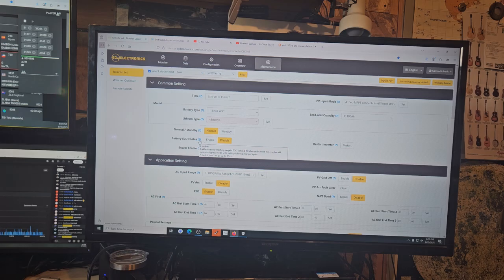Okay, so if enabled, when battery reaching on-grid EOD value and AC charge disabled, the inverter will switch to bypass mode until battery is being charged again. That may be a setting we might have to explore.